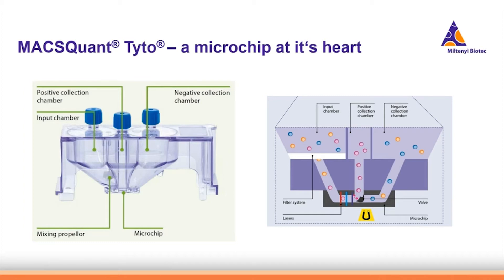On the right side we see this in more detail. Cells are coming from the input chamber into the channels of the microchip. They are crossing the laser beams, and if the system recognizes the target cells, a pulse will open the valve and the cells will go to the positive collection chamber.